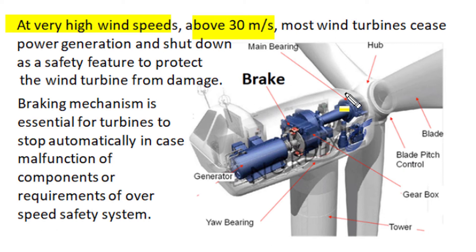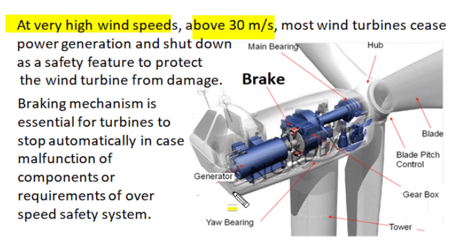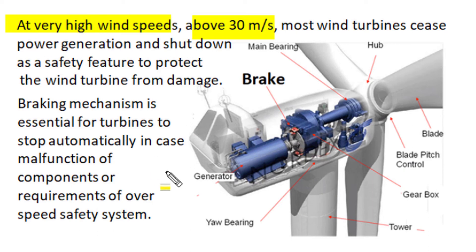At very high speeds above 30 meters per second, most wind turbines cease their power generation and shut down as a safety feature to protect from damage. The blade pitch control changes the orientation of the blades, the yaw mechanism changes the orientation of the nacelle bed, and the backup mechanical braking mechanism stops the turbine generator. This action is performed whenever there is very high wind speed or an electrical fault in grid connectivity.